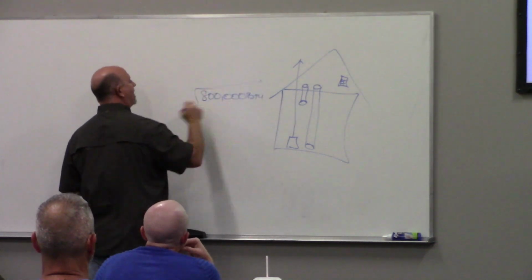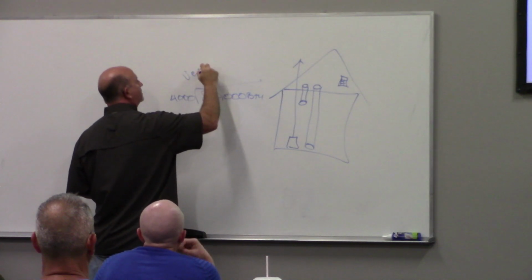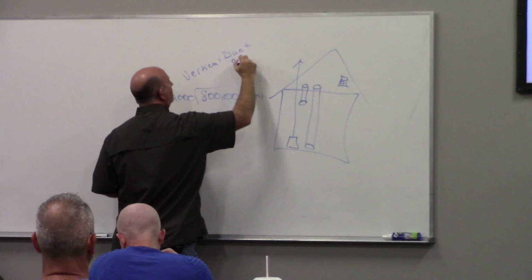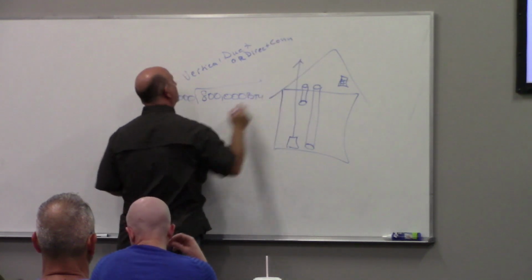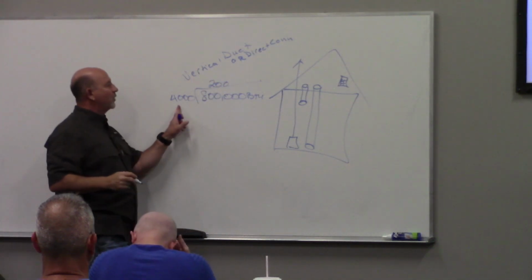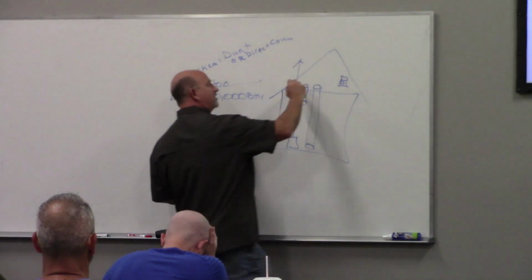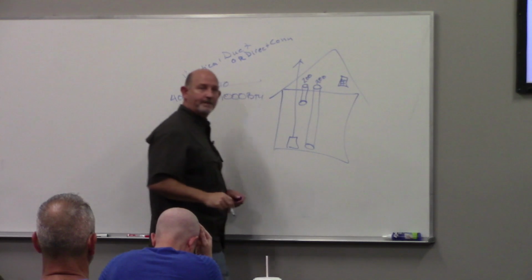I would divide that by 4,000 BTUs if it's a vertical duct or direct communication. Right? So 800,000 divided by 4,000, that's 200. I've got 4,000 BTUs 200 times, so I need 1 square inch 200 times. So this hole needs to be 200 square inches of area. This hole needs to be 200 square inches of area.